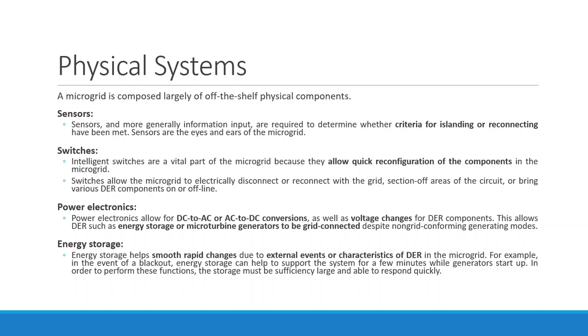So when you are generating in DC and you want to connect it with the AC grid, you need power in AC at the same frequency. If your grid is 50 hertz, then you need the AC at 50 hertz, and then it can be connected to the grid. This capability is provided by the conversion system, DC to AC conversion. So basically this enables the energy storage or micro turbine generators to be grid connected despite non-grid conforming generating modes. Maybe it is not as per the grid requirement, but this makes it compatible, you could think of it that way.